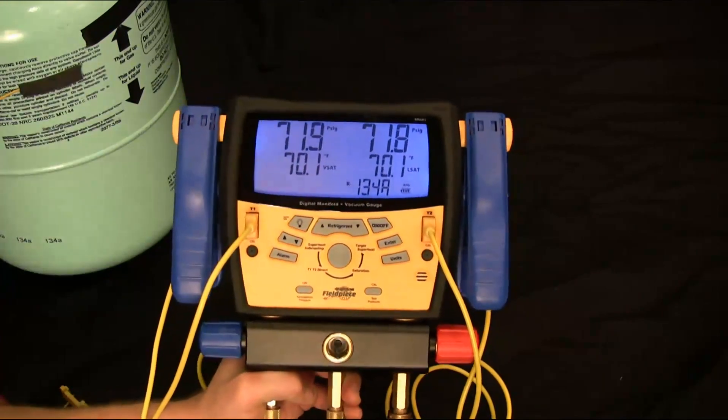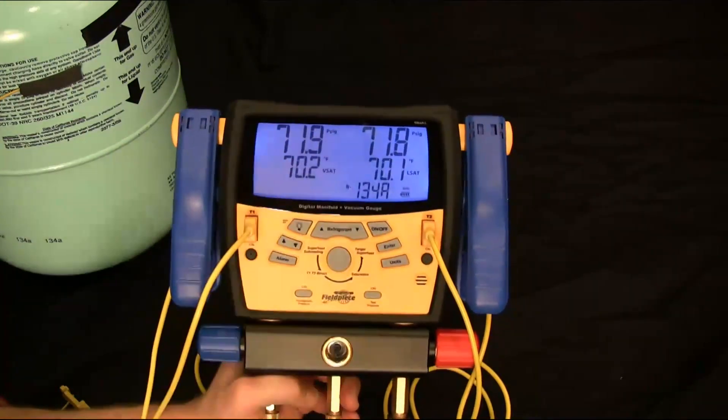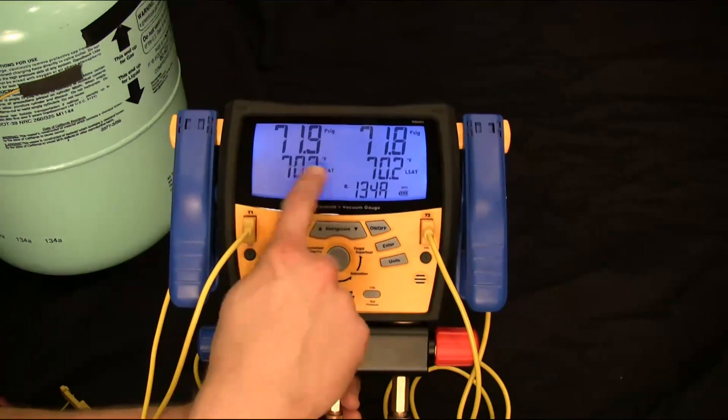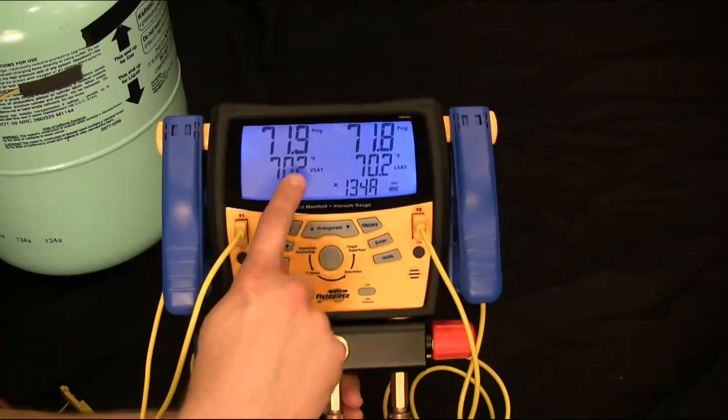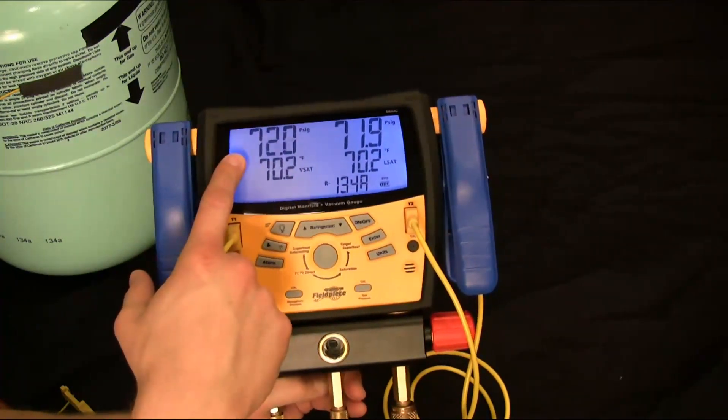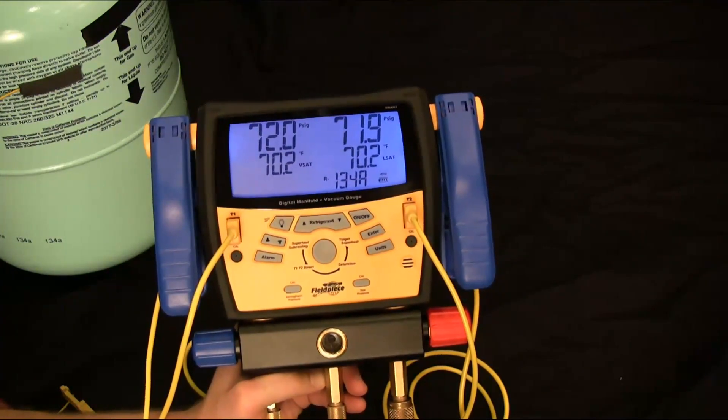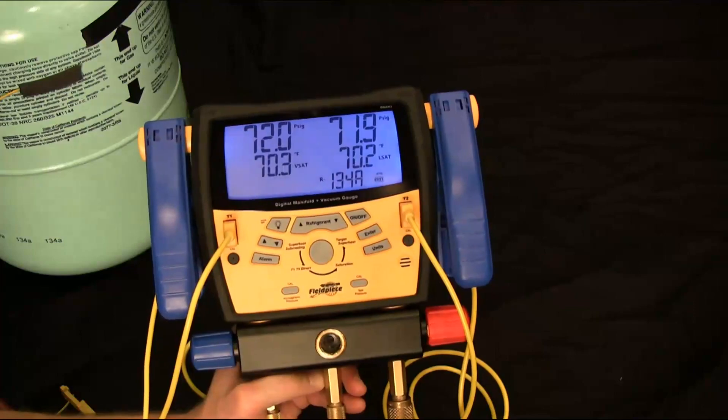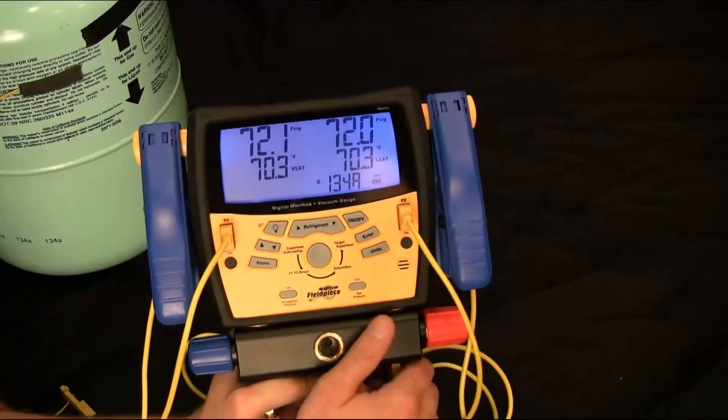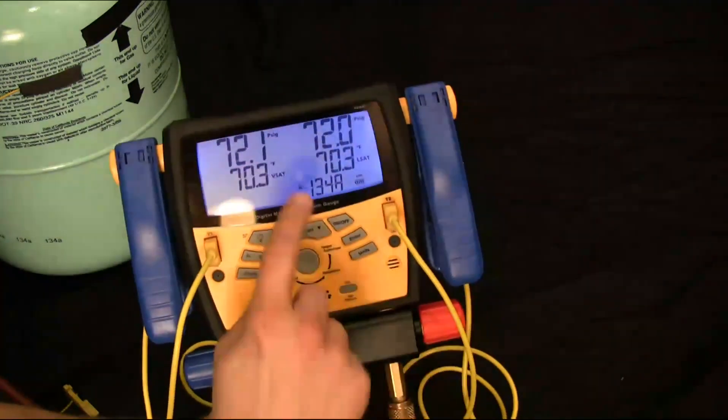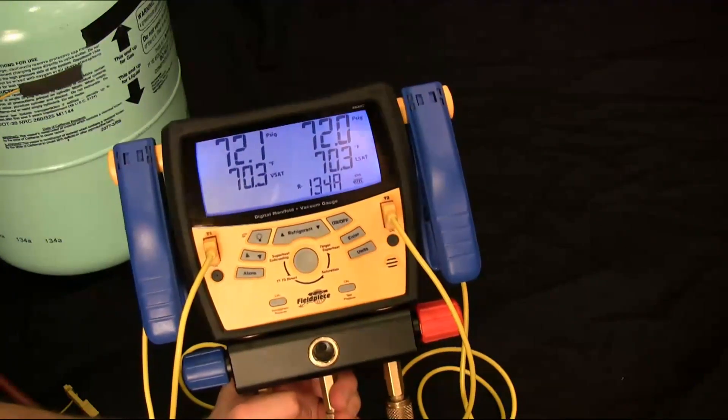All right. And you'll see that I got a pressure display right on the top right here. Now the vapor saturation, what this is telling you is at 71.9 psig, it boils at 70.2 degrees. So it's basically pretty close to its boiling point right now. And then same thing with the liquid saturation temperature.